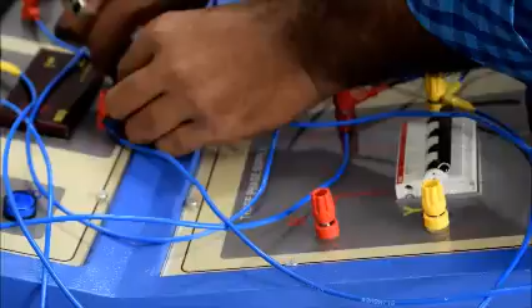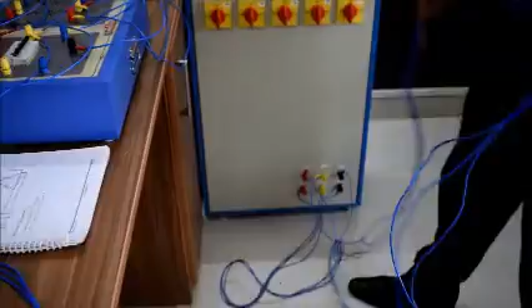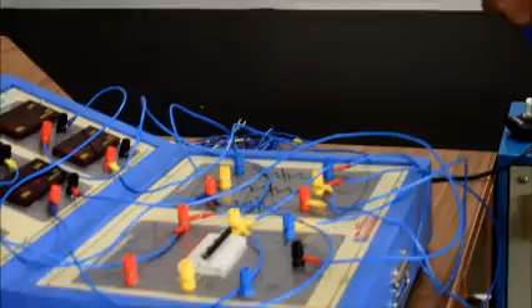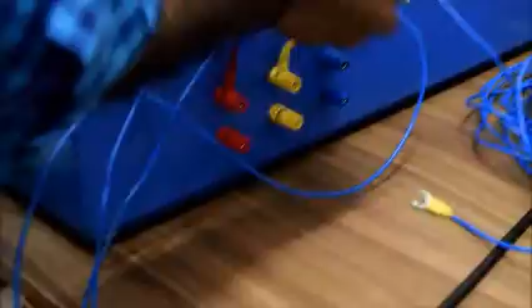Now I need to connect the loads from this load bank to this kit. I'll hold the upper terminal. These wires indicate all three coming from the upper terminal. There is insulated tape over here for R phase, Y phase and B phase, so directly from this insulated tape I can identify where to connect it. As mentioned earlier, I need to connect this to the upper terminal of the R phase, then Y to Y, then B to B.